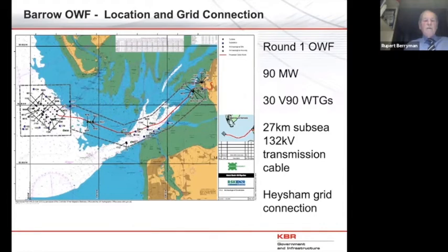Then we bid for a wind farm off Barrow, and by that time we were up to 3 megawatt wind turbines. You can see the position of the wind farm - 2 rows of 7 turbines and 2 rows of 8 turbines, daisy chained together with subsea cables, and a long power cable leading to shore. The nearest point of land was fairly close to the wind farm, but the grid, the Cumbrian ring, wasn't strong enough to take the output from the wind farm.